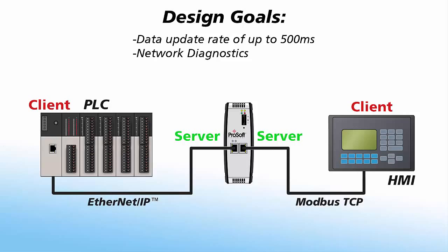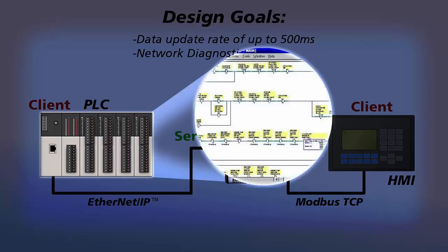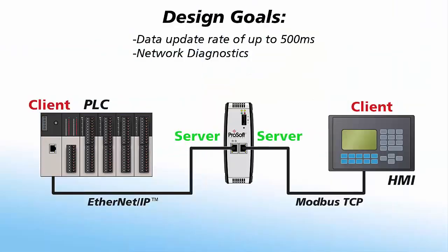have been completed. In addition to this, it should be pointed out that PLC message timing is dependent on ladder code execution. So regardless of having a lower priority, the messages cannot be sent faster than it takes the processor to cycle through the ladder file. As a result, there is potential for this arrangement to have some variation in communication speed. This is acceptable for this application because HMI communications will not be outside our requirements of under 500 milliseconds.